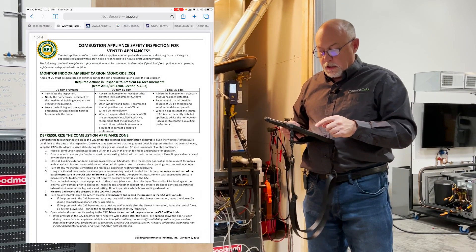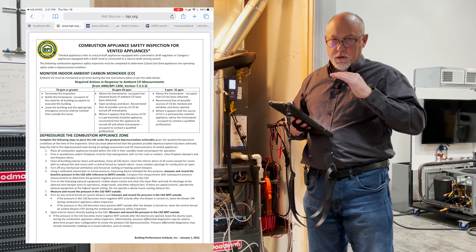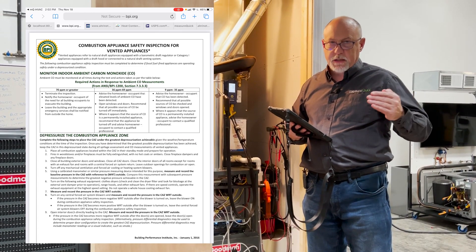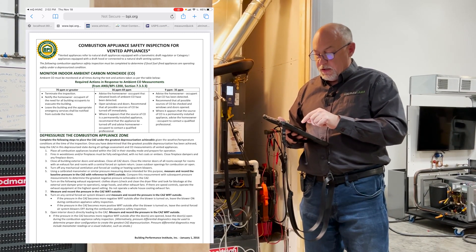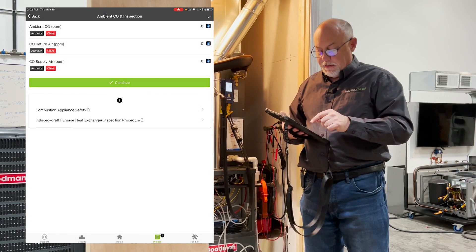We've also got in here our combustion appliance safety inspection for vented appliances. If you're new to doing combustion analysis and you don't know what the CO readings mean or you don't know when to have a call to action — in other words, when to do something — it's in here. It tells you what to do in the lower ranges all the way through the higher ranges, when to terminate the inspection, and when to close out the equipment.